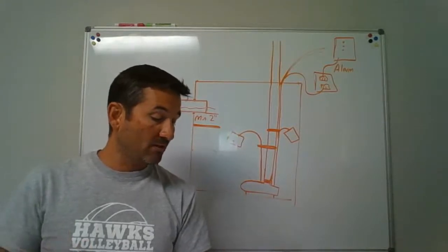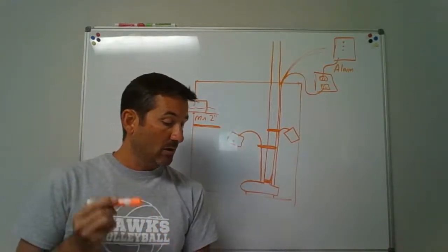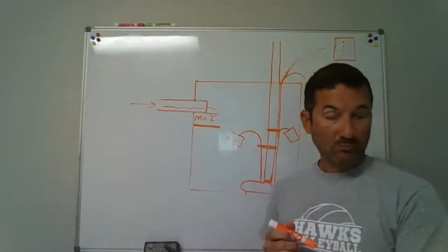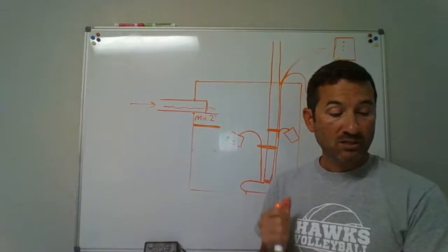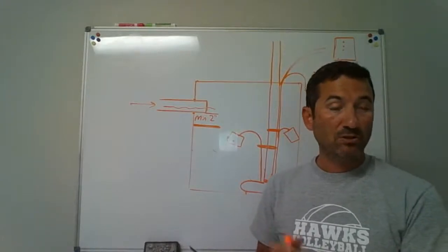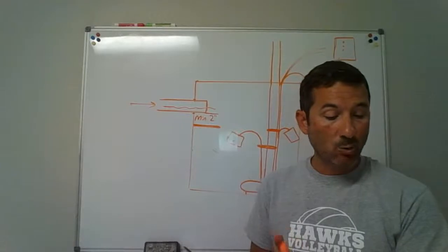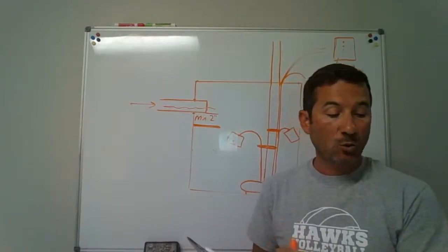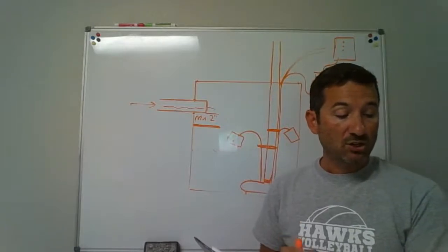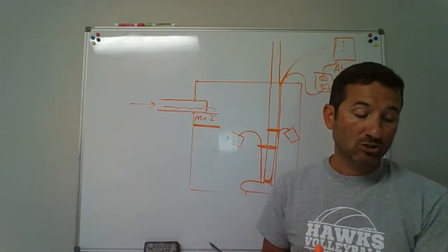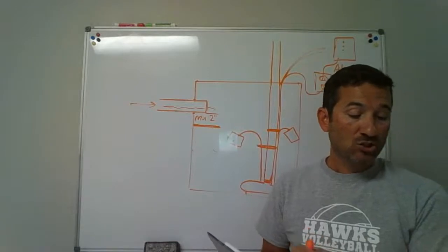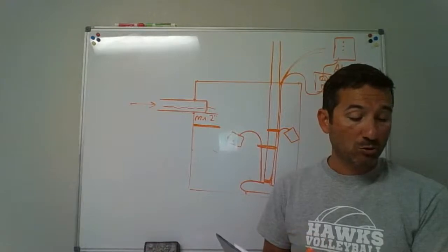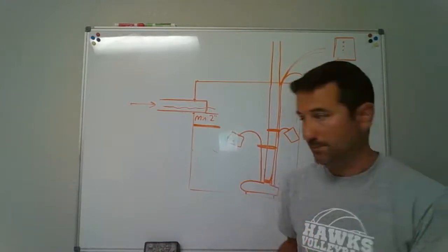It says, how do I make the pump connection to the drainage system? This is over in 712.3.5 at the top left, about page 70. Pumps connected to the drainage system shall connect to a building sewer, building drain, soil stack, waste stack, or horizontal branch. It says, where the discharge line connects to the horizontal drainage piping, the connection shall be made through a Y fitting into the top of the drainage piping, and such Y fitting shall be located not less than 10 pipe diameters from the base of any soil stack, waste stack, or fixture drain.